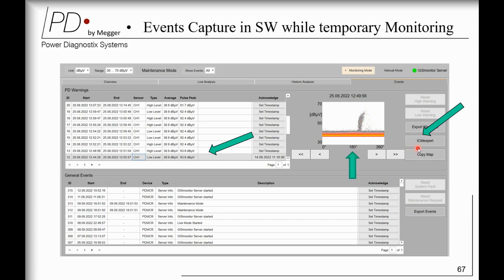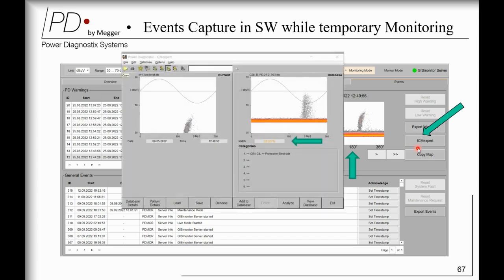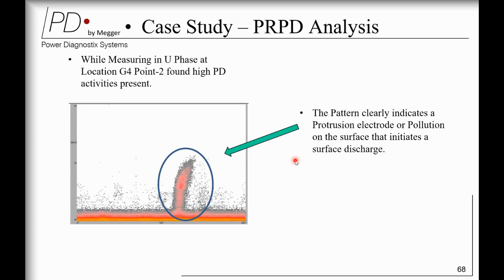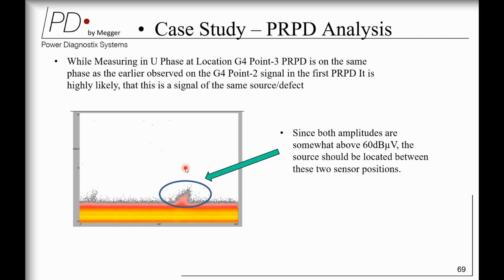Then I used the ICM expert software for the analysis, and the software also helped me understand what type of PD I have. It also identified protrusion, which means there is some sharp edge in the GIS. So we recommended the customer do PD monitoring over a period of time, temporary monitoring. This is one of the images. The location was G4.2, where the UHF sensor captured the PD. It looked like a protrusion or also like a surface discharge, which initiates this PD activity. We also captured the PD in the next UHF sensor, where it was clearly seen in that particular compartment.